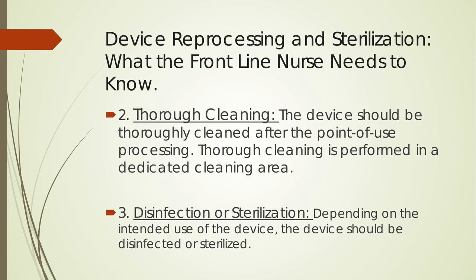Step two is thorough cleaning. The device should be thoroughly cleaned after the point of use processing. Thorough cleaning is performed in a dedicated cleaning area. It is not performed in a hand washing sink or in a clean area, a dedicated area. Usually this area is identified in central processing as the decontamination area, where proper personal protective equipment or PPE and ventilation requirements are in place.